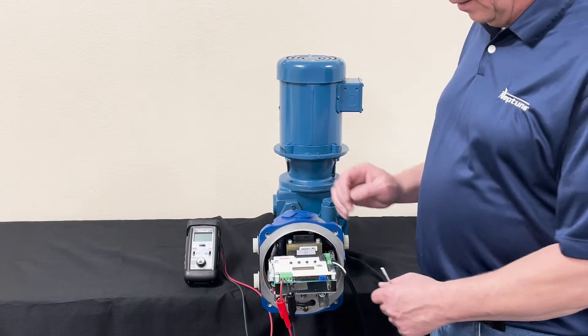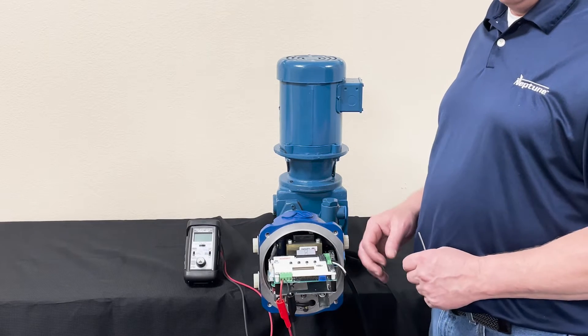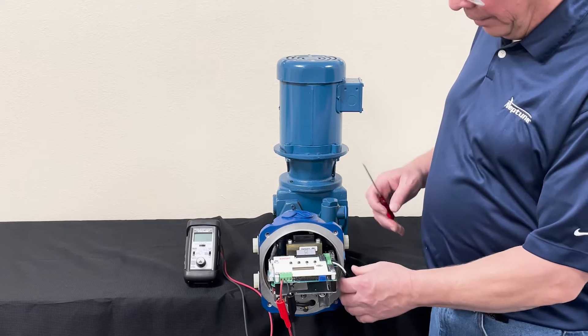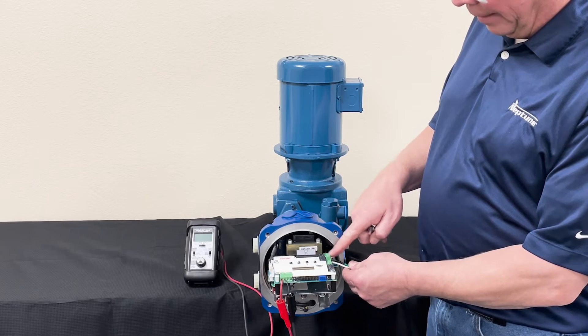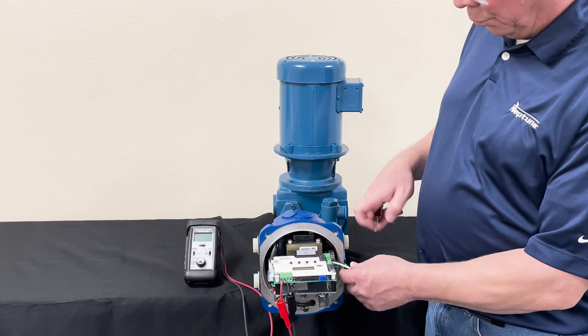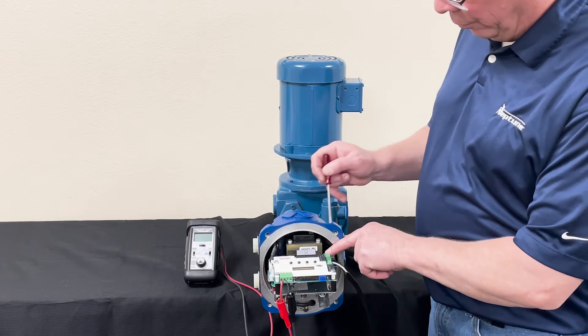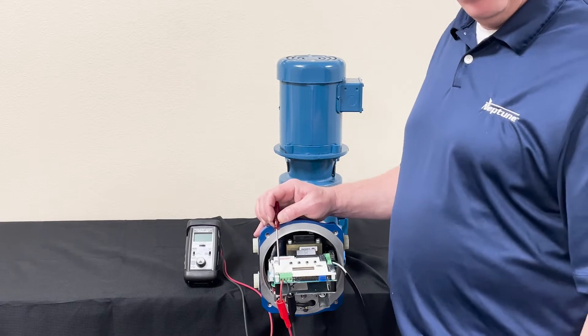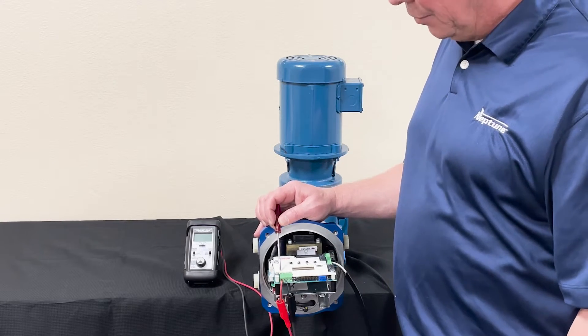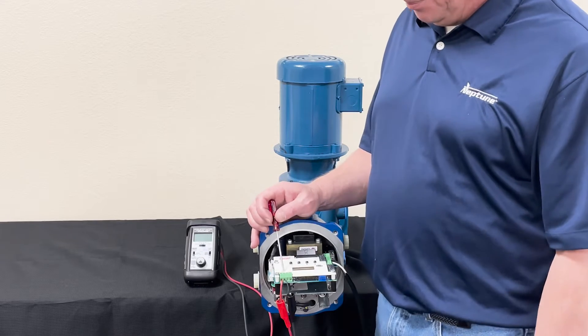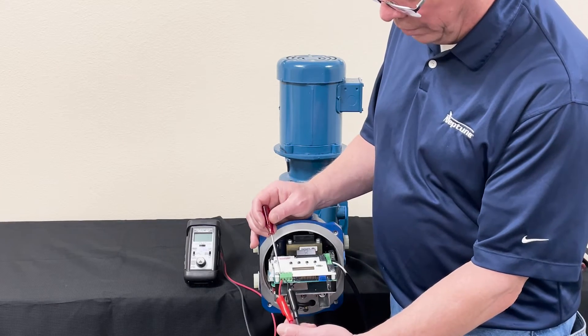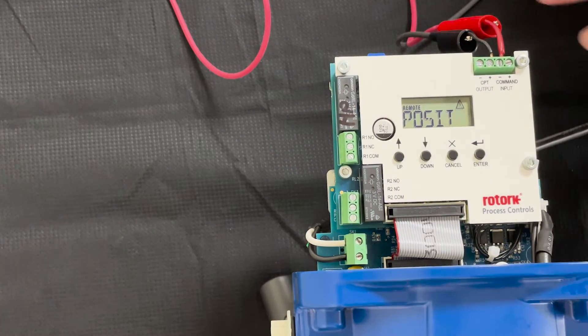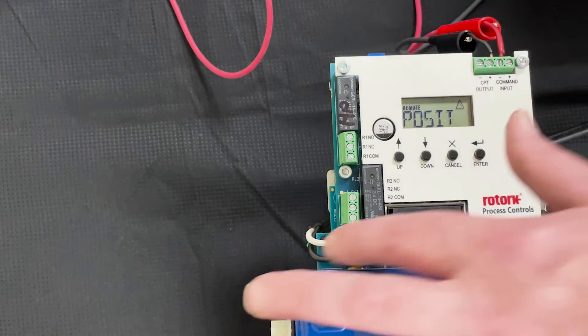When it slides off, you'll come to your connections. The controller can be powered up by using single phase 115 to 220 volt by connecting your neutral and your hot connections to L and N on the backside connectors. Your input command, which is your analog 4 to 20 milliamp signal, comes in here on these two connections. We have our wires for our analog and our power connected.